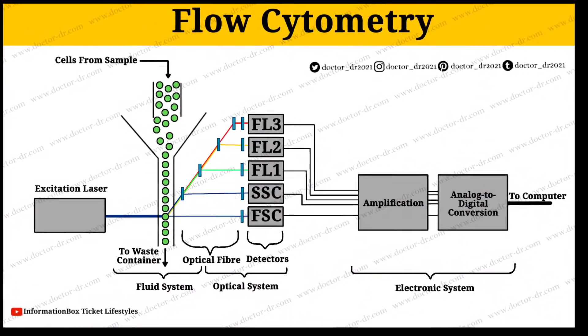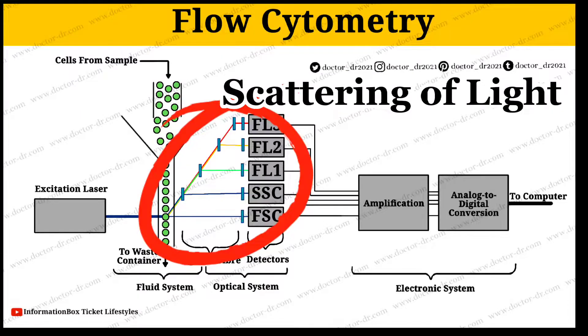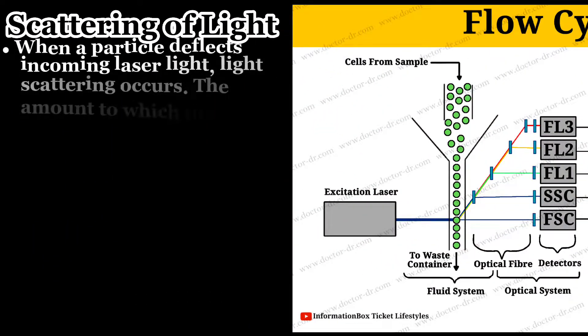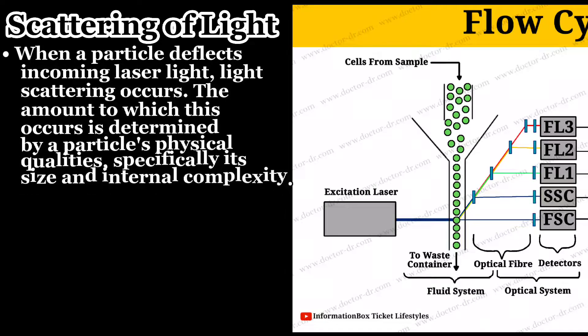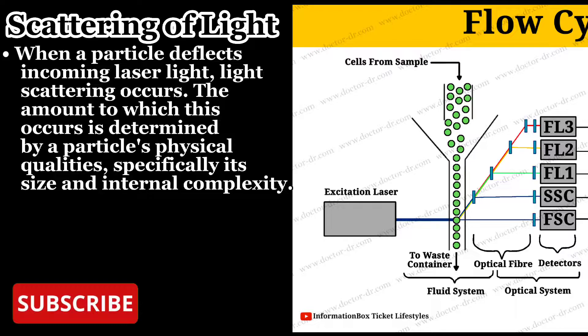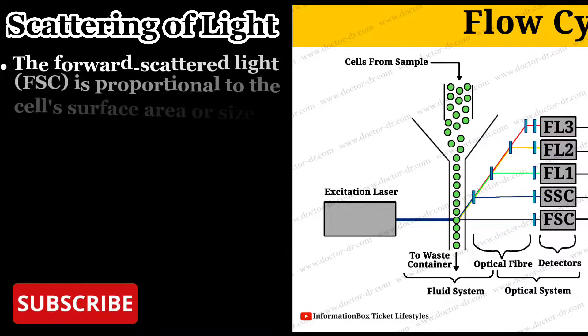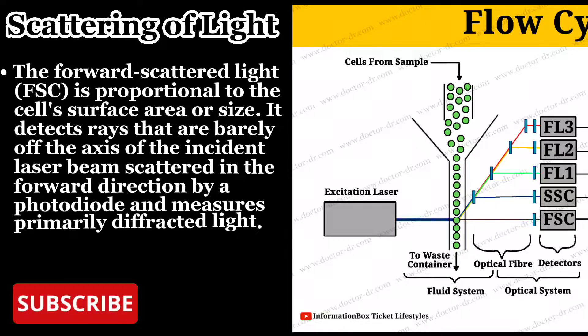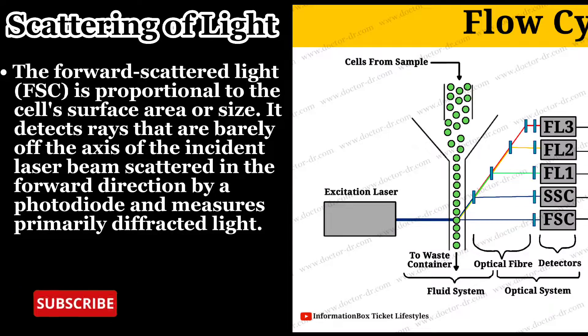Let's now briefly understand the process of scattering of light. When a particle deflects incoming laser light, light scattering occurs. The amount to which this occurs is determined by a particle's physical qualities, specifically its size and internal complexity. The forward scattered light (FSC) is proportional to the cell's surface area or size — it detects rays that are barely off the axis of the incident laser beam, scattered in the forward direction by a photodiode.